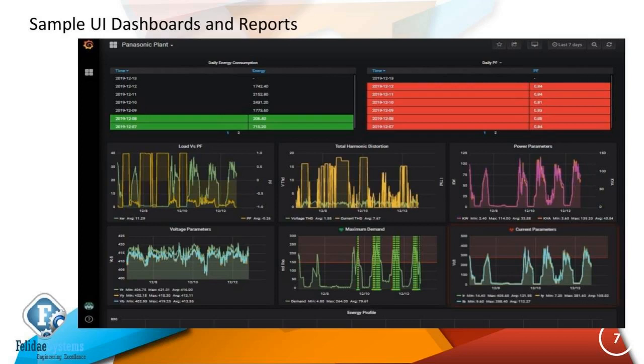Similar to that, the third parameter is power factor, which is widely misunderstood by many people. They consider the power factor value from the APFC panel - that instantaneous reading - as what the power factor is, which is not the case. If you're seeing it's 0.99 right now, we don't know if this is for the whole day or not.